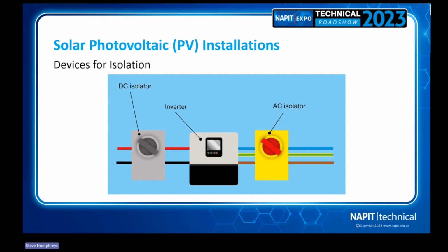So there could be an argument that if that array from the roof, the only means of isolation is in the loft or perhaps on the roof itself, you could have then live DC cables with hundreds of volts coming into your inverter with no other means of isolating it if you can't get up to that roof. So we at NAPIT would always say, would rather fit them. We're speaking to contractors about that and our members, and seeing what the consensus is. So it's not a blanket thing. There was a document from the FPA, which was RC62, that said eliminate DC isolators where they're installed on the inverter where possible, but everyone seems to be forgetting the where possible bit.